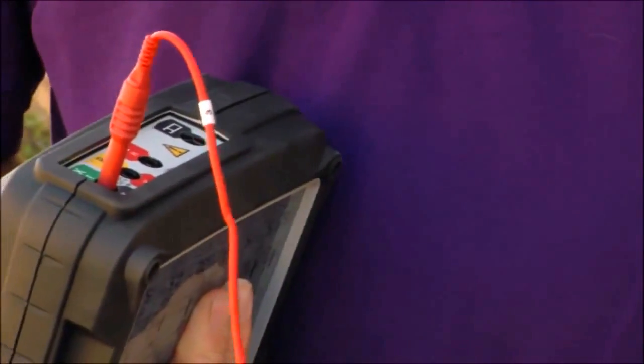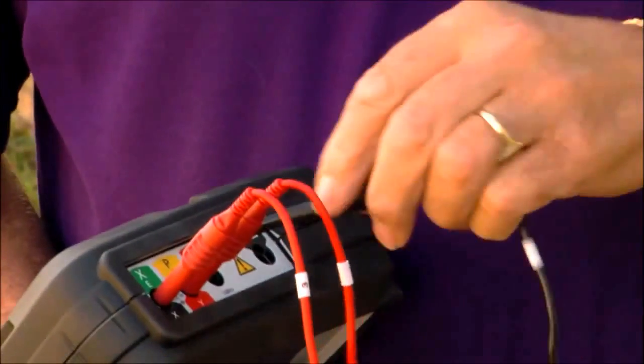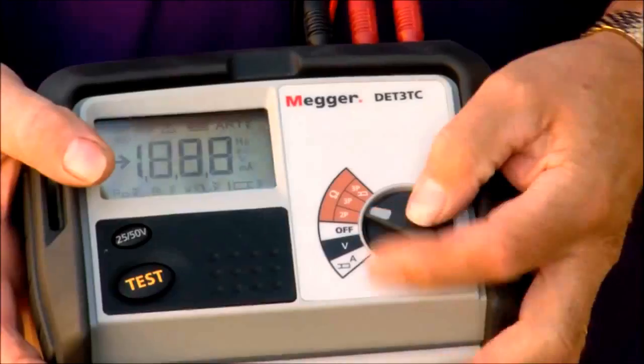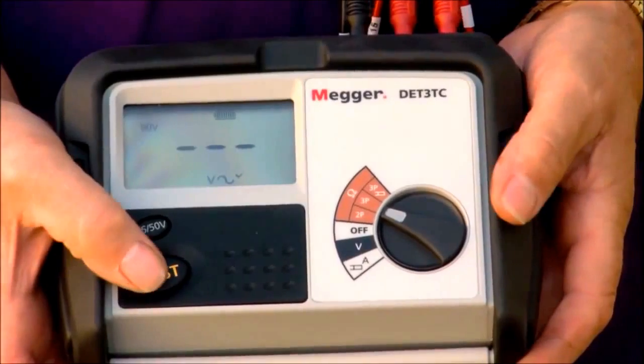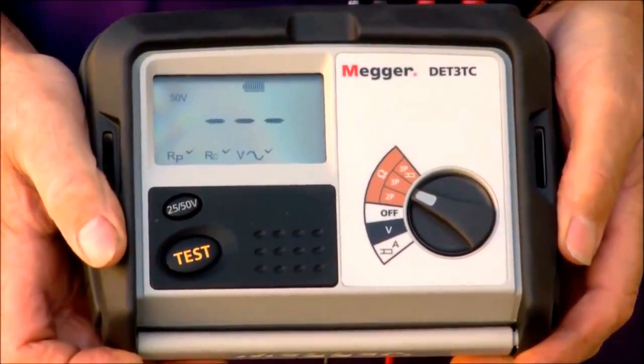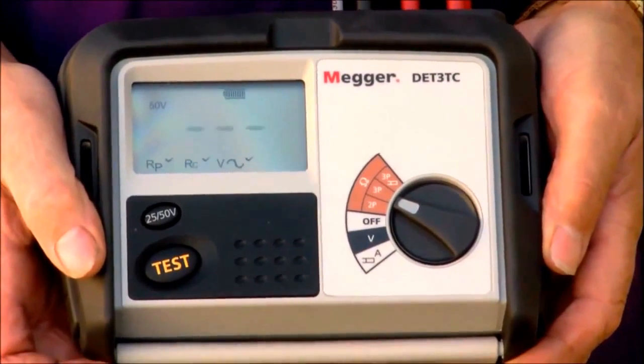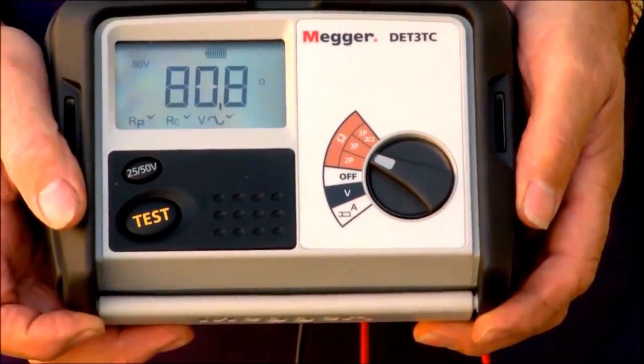The current electrode, which is the furthest one away, needs to be at least 10 times the depth of that electrode away, and the potential electrode needs to be placed in between the two. I then need to connect the ends of the leads into an earth electrode test instrument and take a recording of the resistance value. This is a 3-lead test, so I just need to give the machine a second or two to settle, push the test button, and you'll see that it's reading the potential electrode and the current electrode. And we've got a resistance value there of 80.8 ohms.